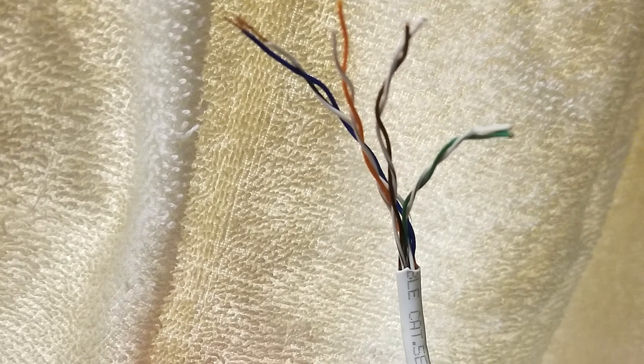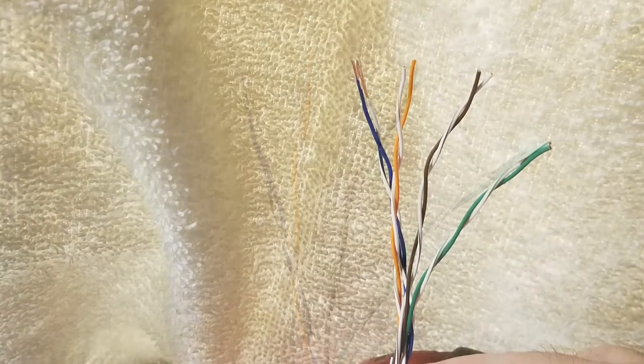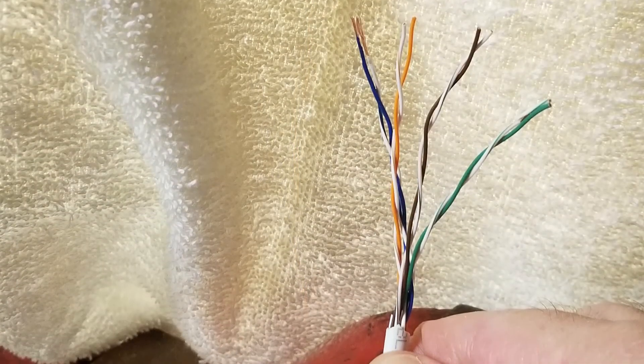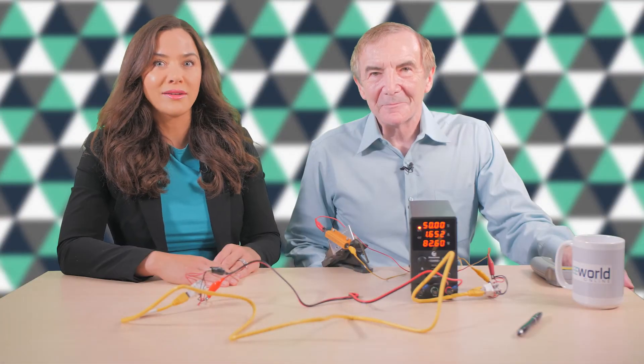Now you might wonder whether a cable originally designed to carry power levels measuring in the hundreds of milliwatts can safely work in an environment characterized by two amps of DC current and loads dissipating 90 watts. If you look at the cable design specifications, they look fine on paper. But to check things ourselves...